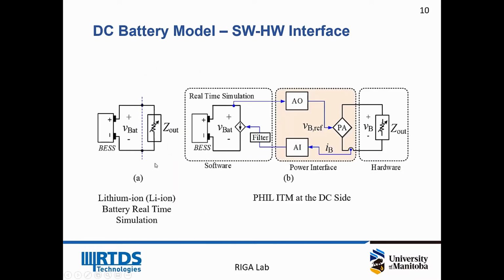On the DC battery side, the power hardware in the system is quite similar to the AC side as well. Inside the software, we have a battery model, so that means we do not have a physical battery. For the hardware, the same, we can model the charger just using a simple impedance. If you take a look at the interface, you will see the same. We have an analog to digital converter and then an amplifier, and it also sends the current from the charger and feeds it back to the software. In the hardware, the amplifier is emulating a battery, and in the software, a voltage controlled current source is emulating the EV charger. And this battery can be different types of battery, and for this study we use a lithium-ion battery inside the RTDS.